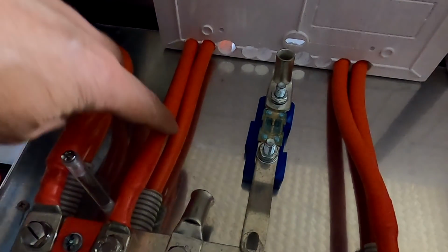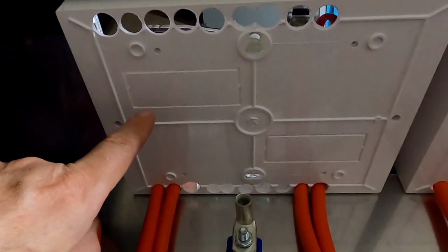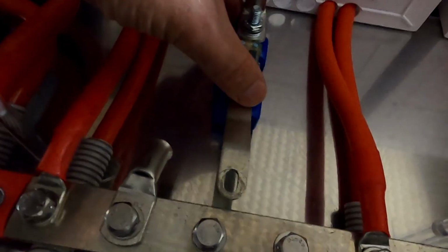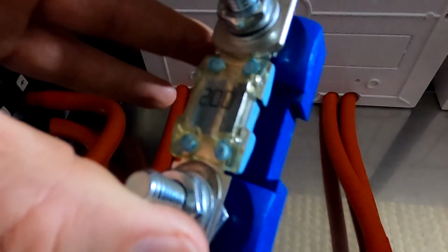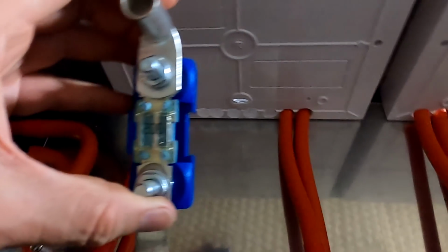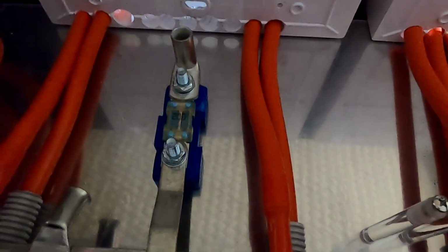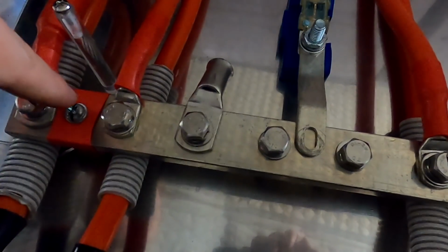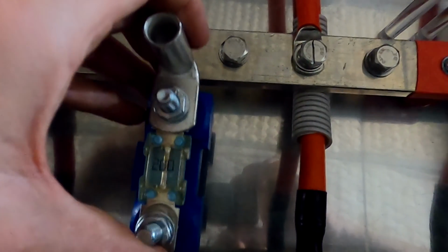And you can see this bus bar fits perfectly over here. Obviously, we need to drill this up to 8 millimeters, so it fits the stud here on the bus bar. So these 2 cables need to come out. This was for our 63 amp circuit breaker here in the front, which we cannot use anymore. And instead we need to put these Victron mega fuses in there with 200 amps capability. That's what they recommend, only in the positive line. And I'm so glad I put the positive bus bar over here. Otherwise there wouldn't be enough space to put this in without touching the other bus bar.